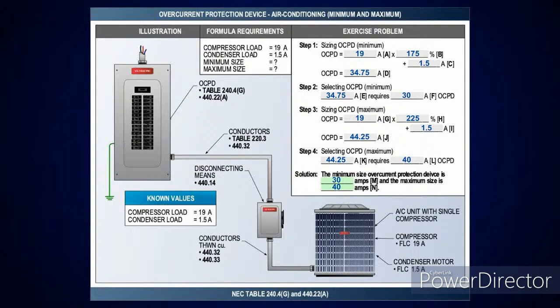Now, a lot of times you can go over and look at an AC nameplate, and you'll see it has the HACR breaker rating, and it'll have minimum and maximum size. Okay. Now, this was an argument that was going on in some of the groups, and they say there's no such thing as minimum. And I said, but yet the industry does do that. And they said, you show me where that happens. And I just posted 3 pictures of the nameplate rating of an AC unit. And someone came on and said the manufacturer can just do whatever they want. I said, you've got to be kidding me. I said, that's not possible.